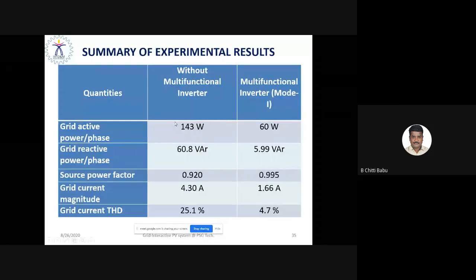Okay, you can see the summary without the multifunctional inverter and with the multifunctional inverter. You can see that the overall system performance is increasing. So active power sharing reduces from 143 to 60. And moreover, reactive power injected into the utility grid reduces from 60.8 VAR to 5.9 VAR, and the power factor improved from 0.9 to almost unity. And the grid current magnitude is reduced largely from 4.3 ampere to 1.66. So the overall THD reduces from 25.1 to 4.7. Of course, it satisfies the IEEE 519 2014 standard.